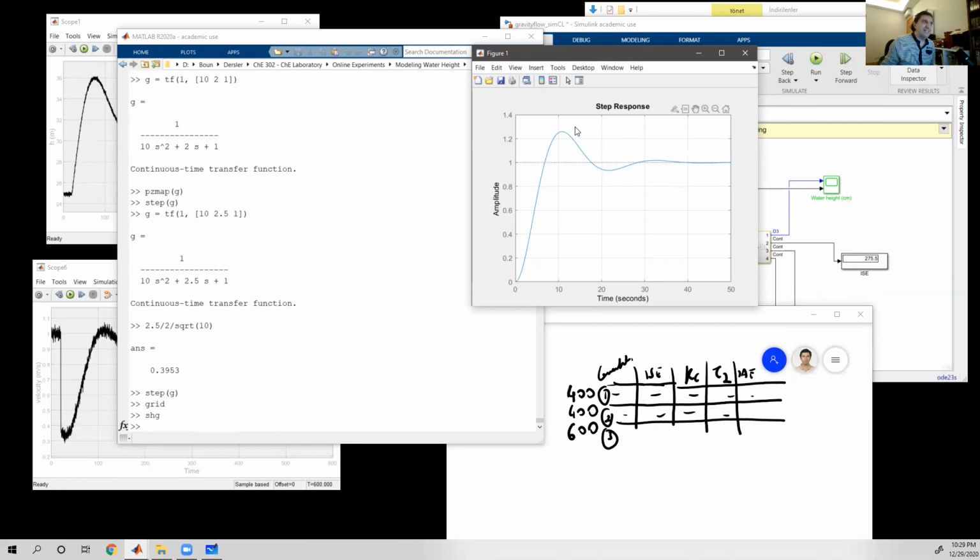So actually try to get associated with the overshoot ratio here, how much overshoot we have here. It is less than 20%. Yeah, it is about 25% of overshoot, right? So the highest peak is about 1.26 and this is 1, therefore we have 26% of overshoot. So basically a 25% overshoot is pretty much tolerable, is pretty much okay for a process.